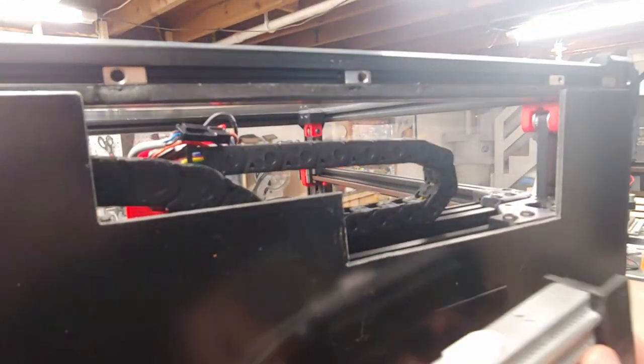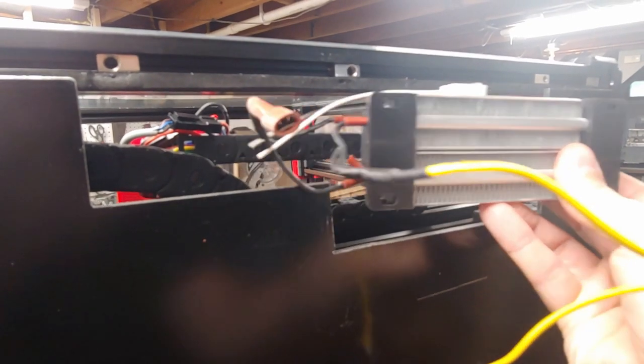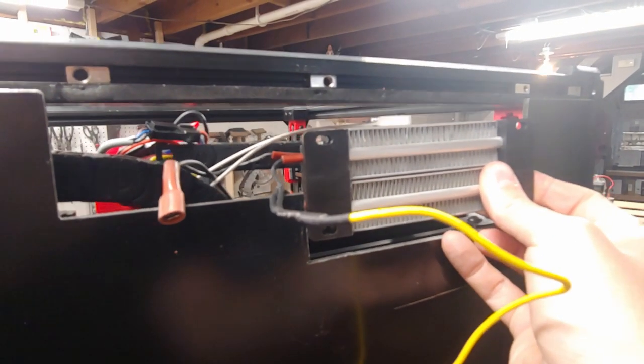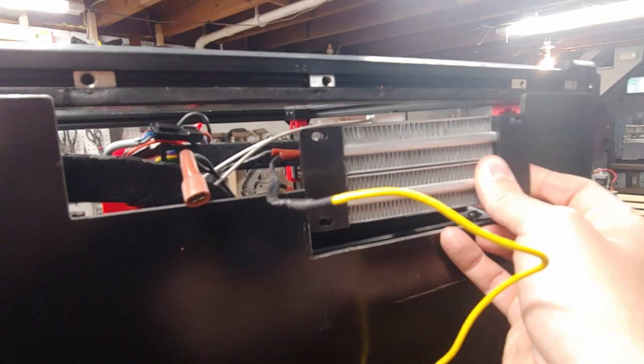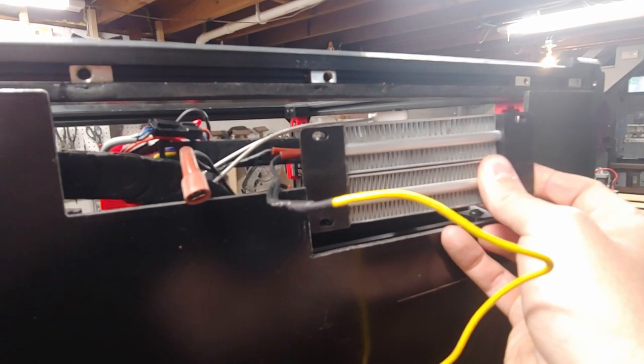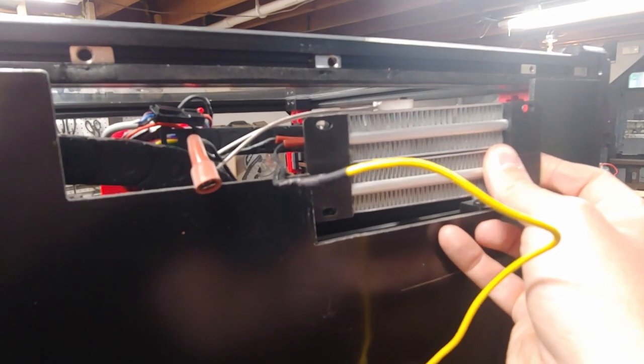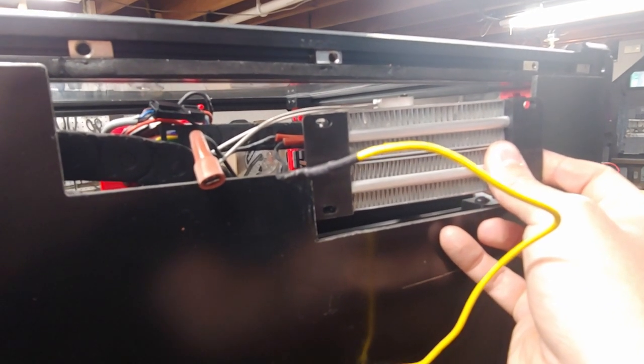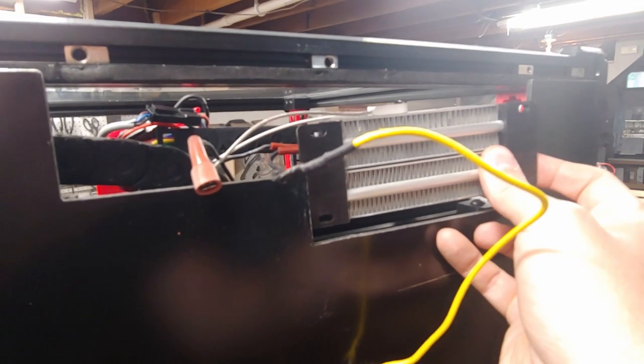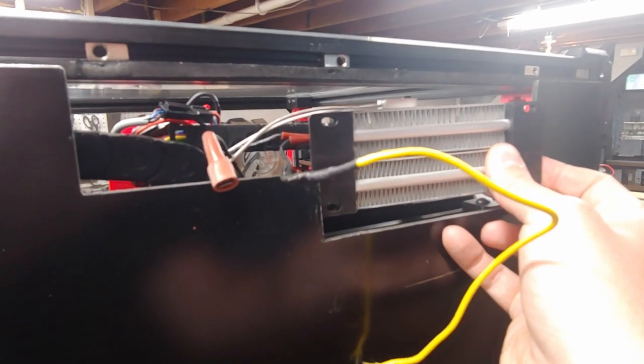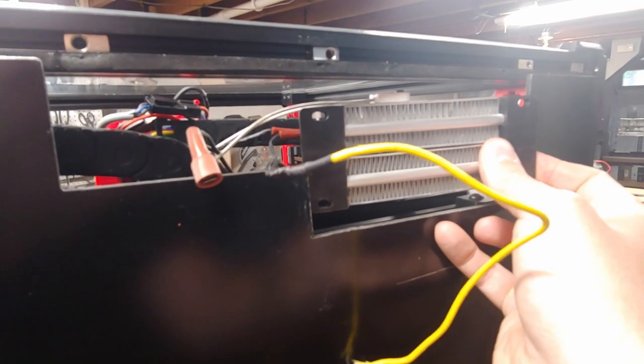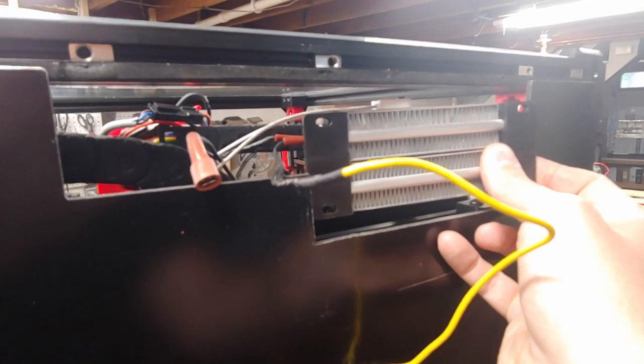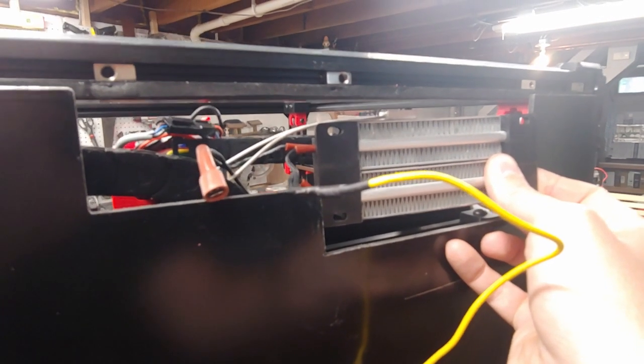Had some extrusions coming down and I kind of placed it in here, attached to the extrusions, but it was a pain in the butt for the ductwork and everything to go around the extrusions. So I've come to the conclusion that I'm okay with it being mounted to the aluminum composite because it's still metal. Probably be a good idea to ground the aluminum composite on both sides in case wire gets frayed or something on the edge if I can't find a grommet to fit.